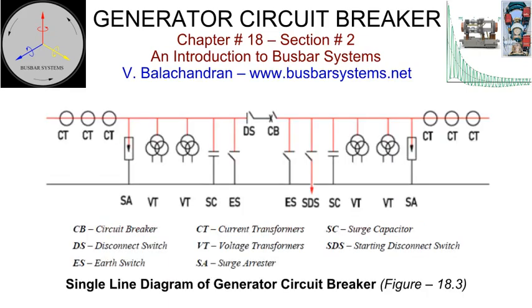A typical generator circuit breaker with associated components that can be installed in each pole is displayed. The generator circuit breaker housing can accommodate current transformers, surge capacitors, disconnect switch, voltage transformers, starting disconnect switch, earth switch, and surge arresters. Any maintenance or replacement of the accessories, if installed in the generator circuit breaker enclosure, will have to be carried out after de-energizing and earthing that section. Many power stations still prefer to have current transformers installed in the run of the isolated phase bus, and voltage transformers with surge arresters and surge capacitors mounted separately in panels.